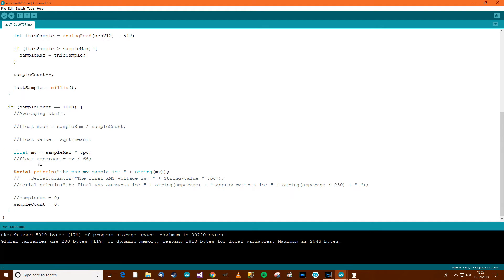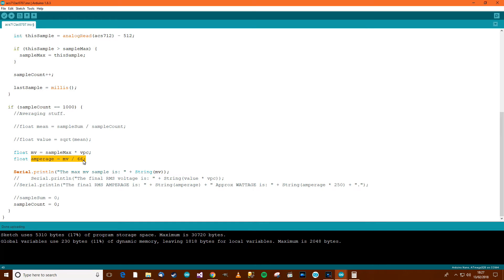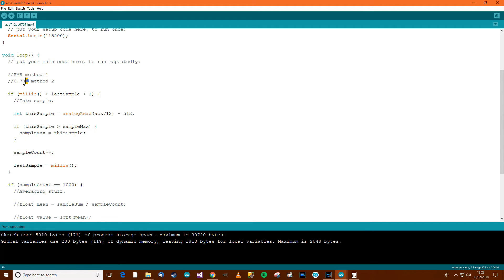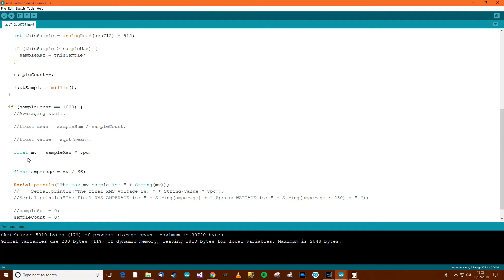The next thing we want to do is find out the amperage from that. But this is where it gets a little bit complicated. It's still not complicated, it's just a little bit complicated. The amperage we've got equals the amount of millivolts divided by 66. But if you remember rightly, that won't give us the actual amperage. That will give us the peak. It's not really an average. It will give us the peak amount, which is not really what we want. We want an average. So what we need to do is use this second methodology, which is this 0.707. So if we get the peak millivolts, we'll change this here to peak millivolts, because that's what it is.